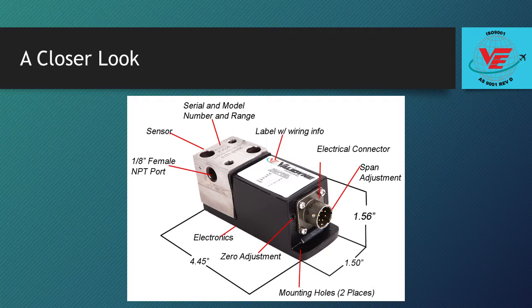The standard pressure port for the P365 is 1/8 inch national pipe thread. A 5/16 straight threaded port is available as an option. In the differential model shown here, the P365 will have 2 1/8 inch pressure ports on each side of the sensor body. These are marked plus and minus.